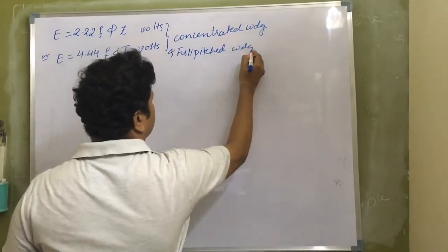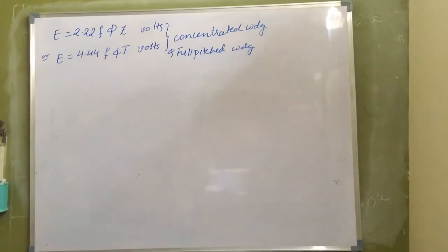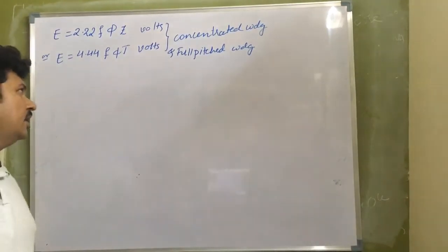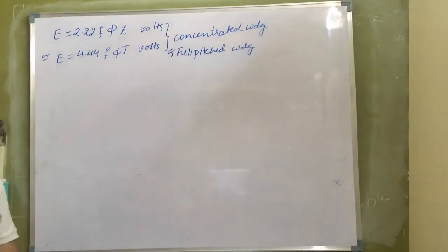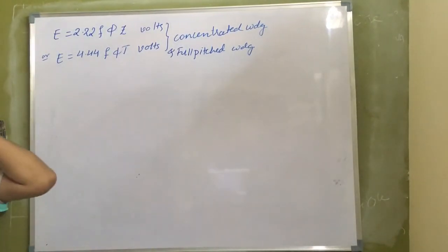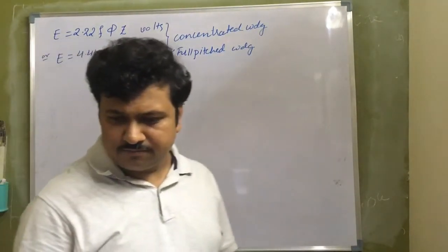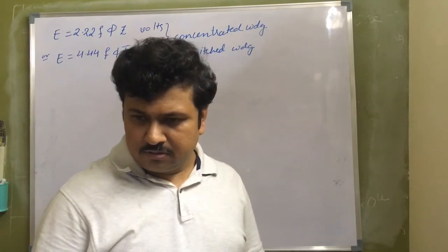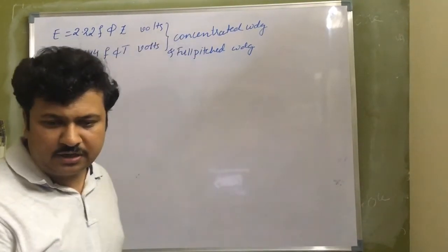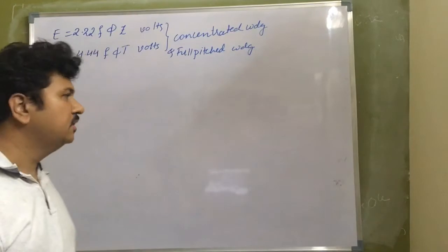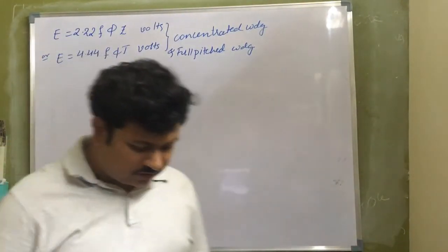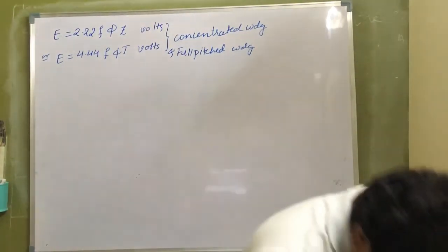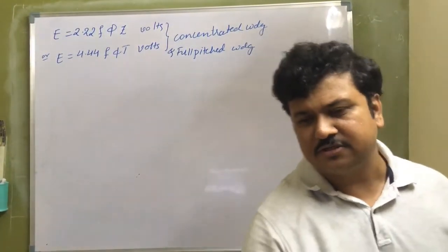Full pitched winding. Okay, so what do you mean by full pitch, what do you mean by concentrated, what do you mean by distributed, and what is meant by short pitch? Okay, we'll see. So the problem with concentrated and full pitch winding is we don't get the induced EMF sinusoidal in nature. So we don't use generally full pitch and concentrated winding in our synchronous generators.